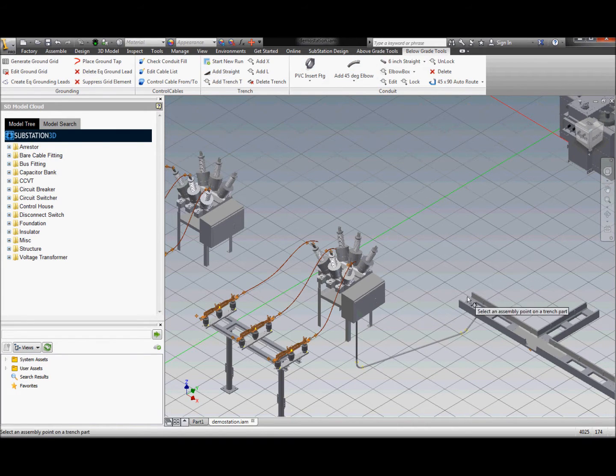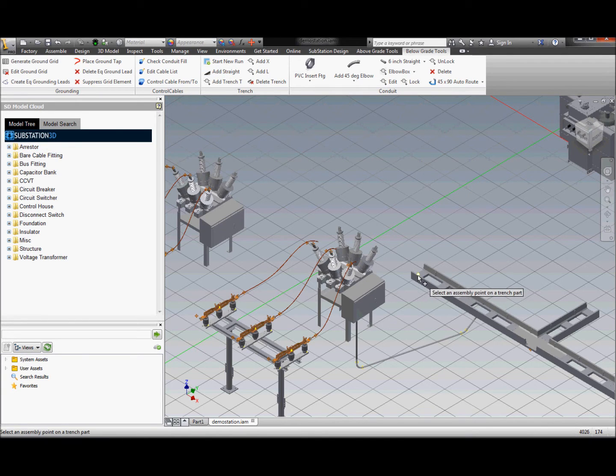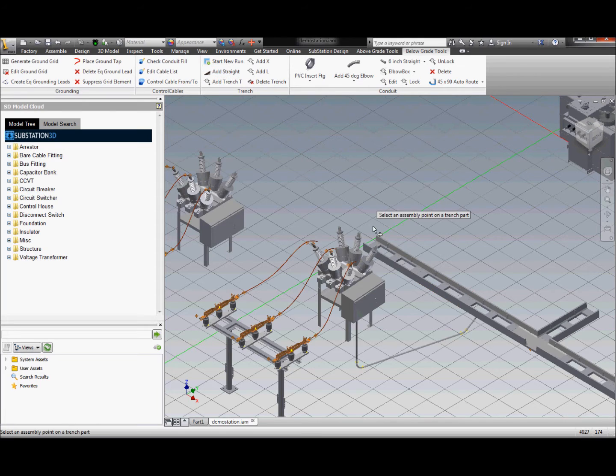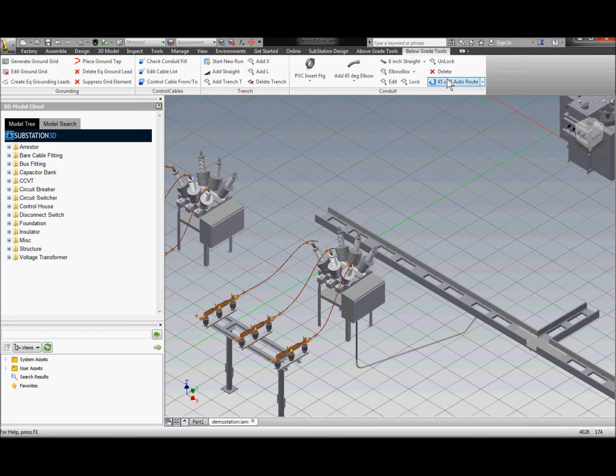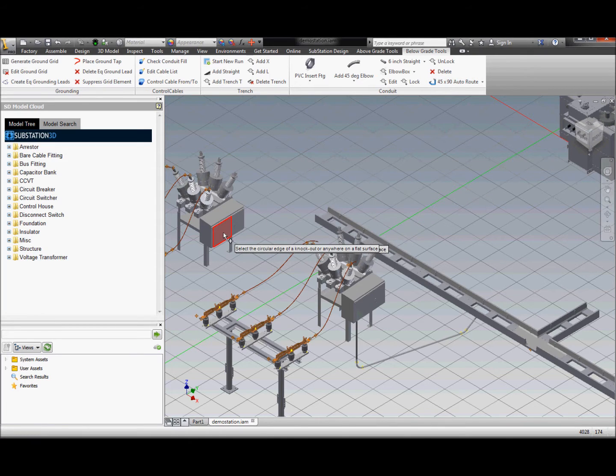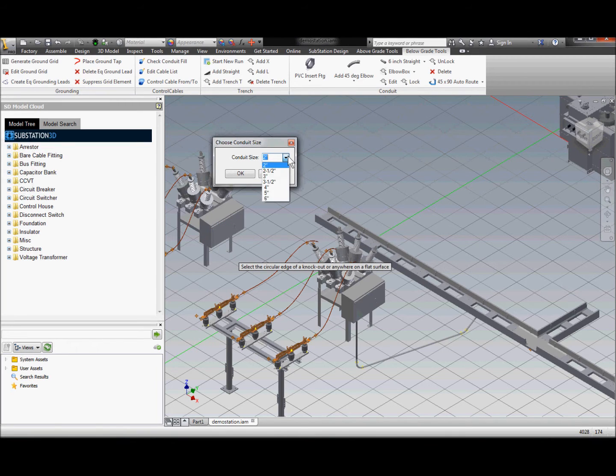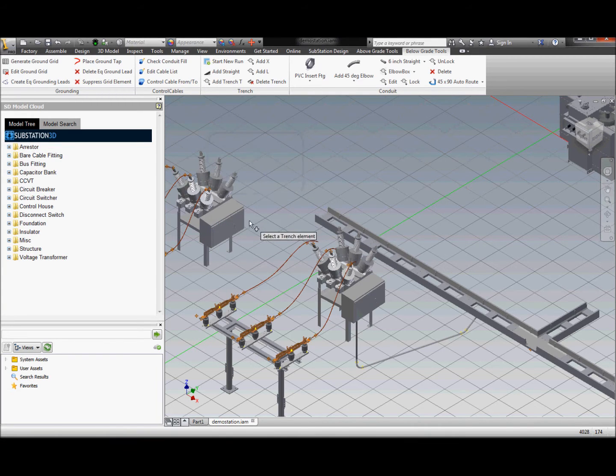Let's continue on, put some more trench components in, and get closer to that other circuit breaker — add a couple more straights and do another conduit run from the other breaker. This reduces the amount of picks and clicks significantly. If you were to do this manually in any 3D system, you'd have to constrain each component, place the parts in space, orient them correctly, as well as add some of the attributes we're using downstream for design checking.